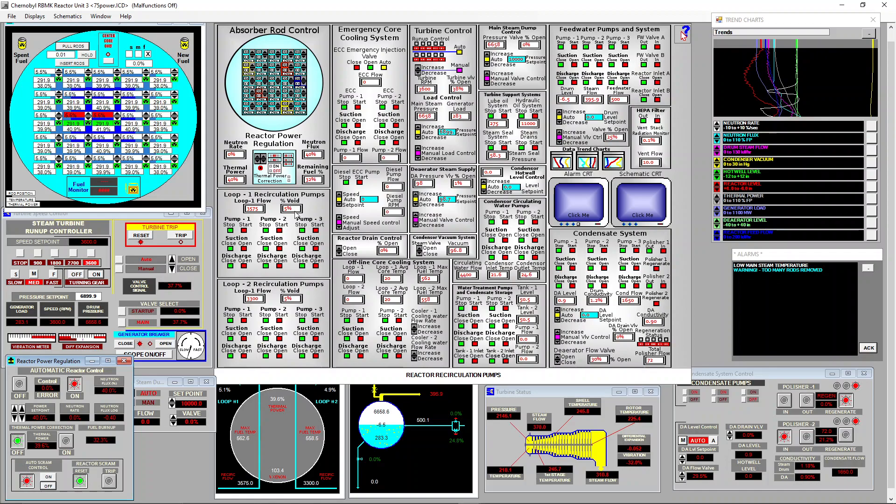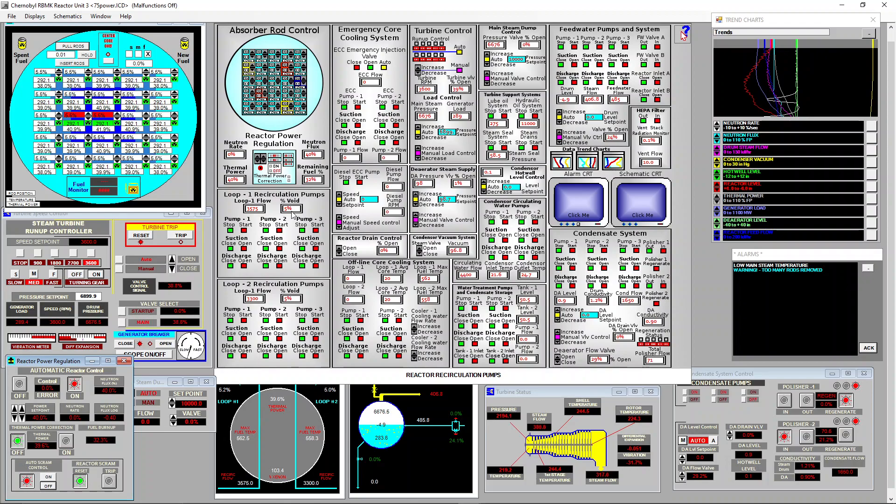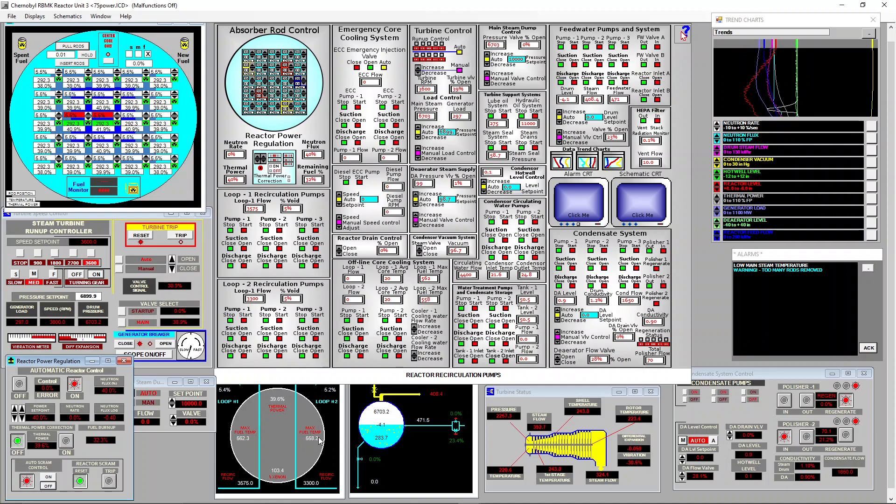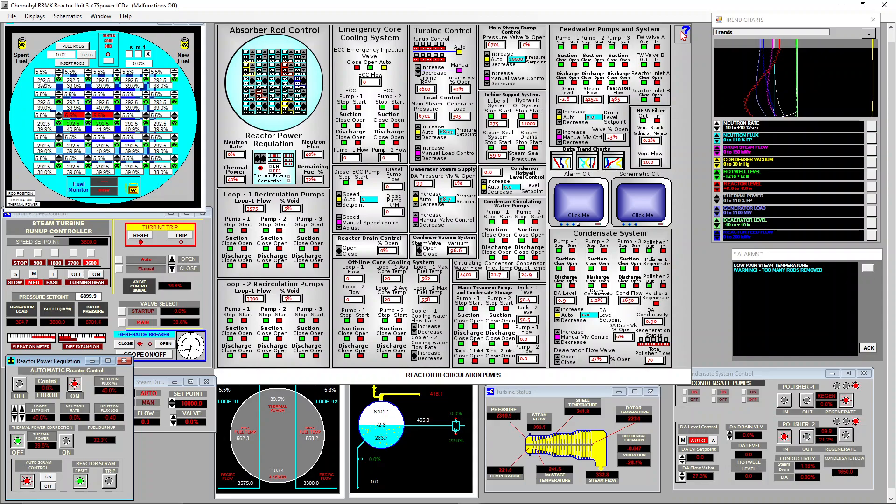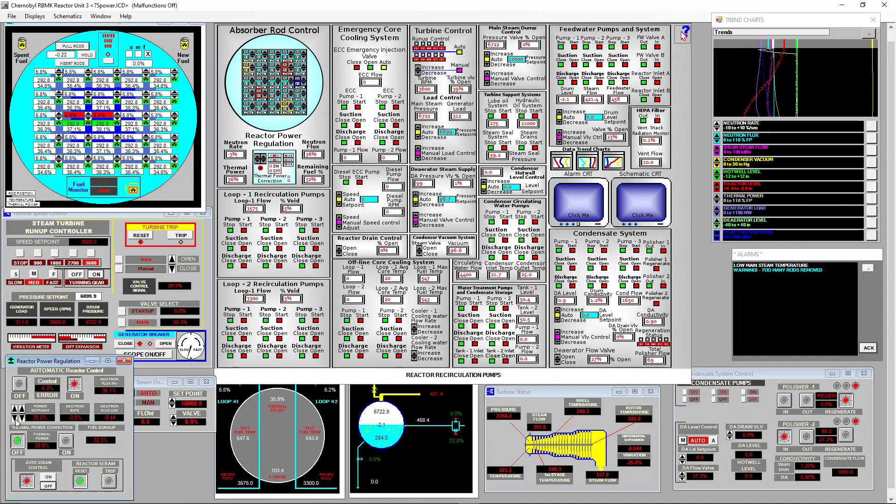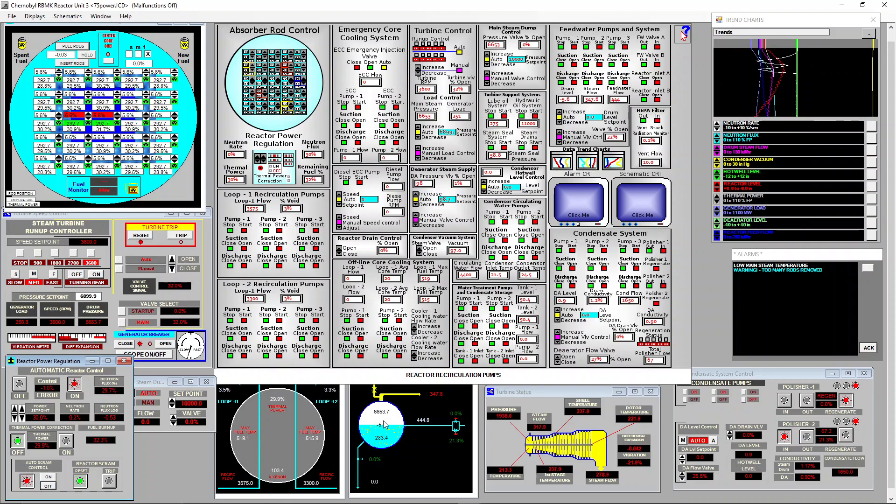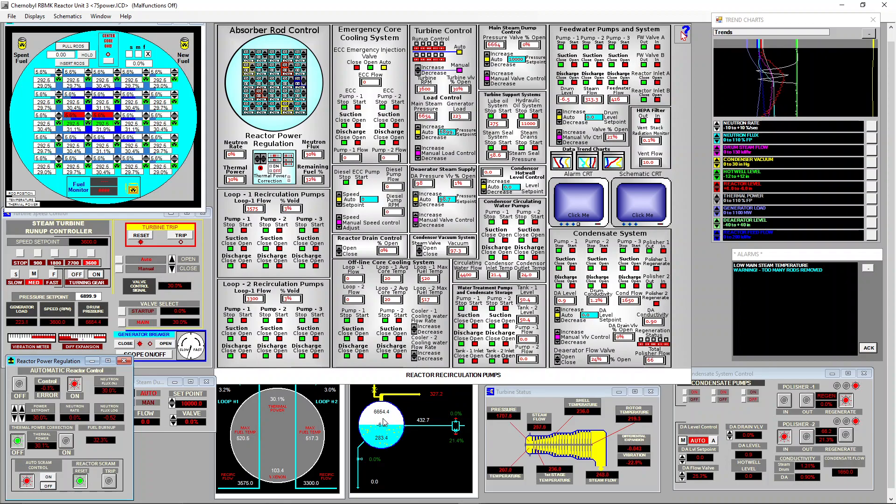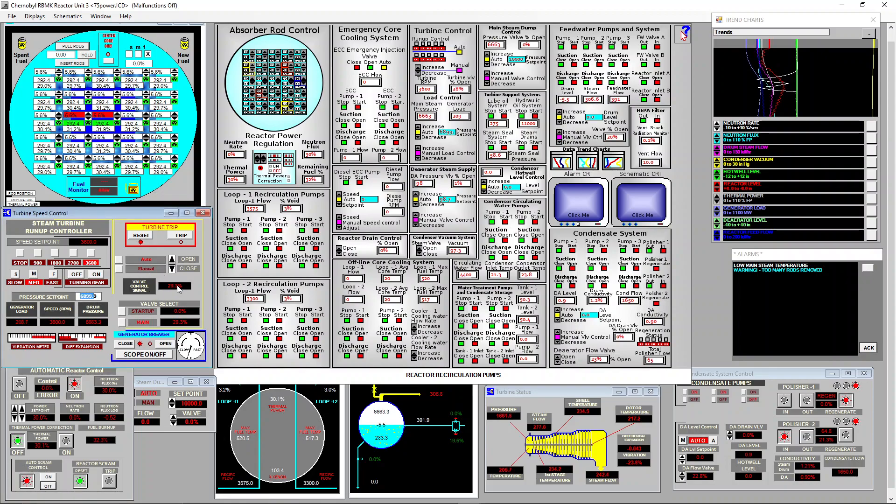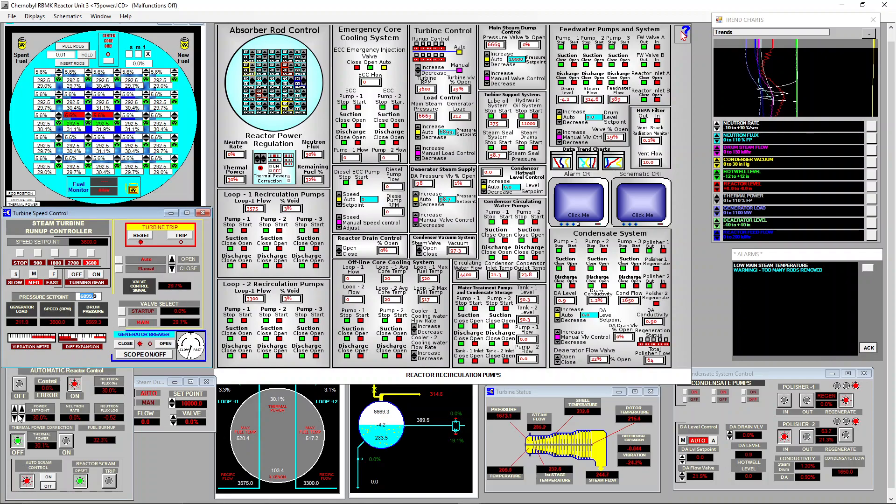It means we are gaining reactivity even if we are drastically reducing voiding. Actually there are several feedback loops, one is voiding but there is also fuel temperature. By reducing fuel temperature you increase reactivity, so this may be significant in the reason why we are slightly gaining reactivity. We'll keep decreasing power, now 35 percent, 30 percent. Generator load we have to start looking at it because we don't want reverse power. Drum pressure is still high because we have accumulated pressure and the control valve is in auto. We should take care that the valve doesn't go close to zero. Let's keep decreasing power, 25 percent.